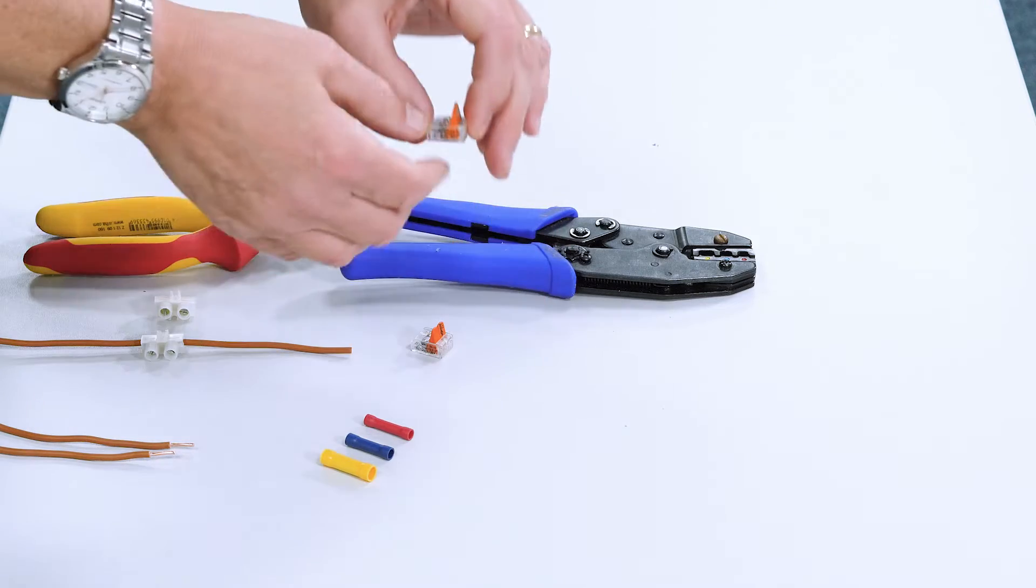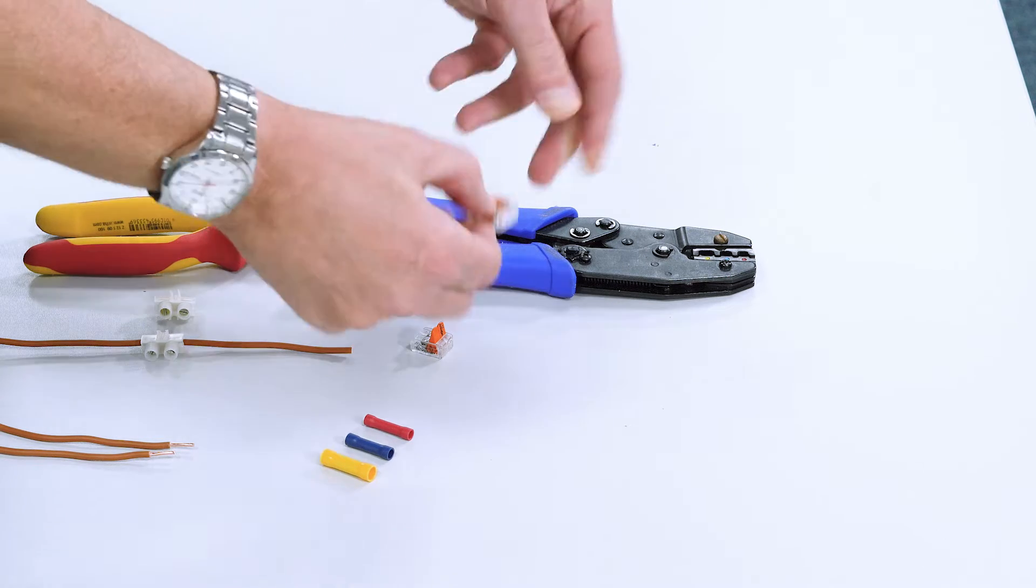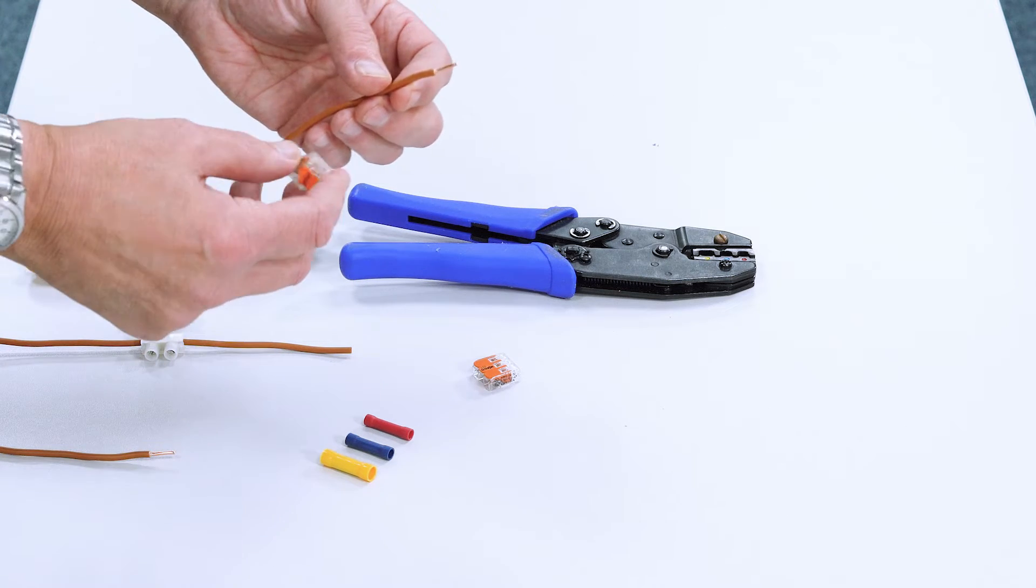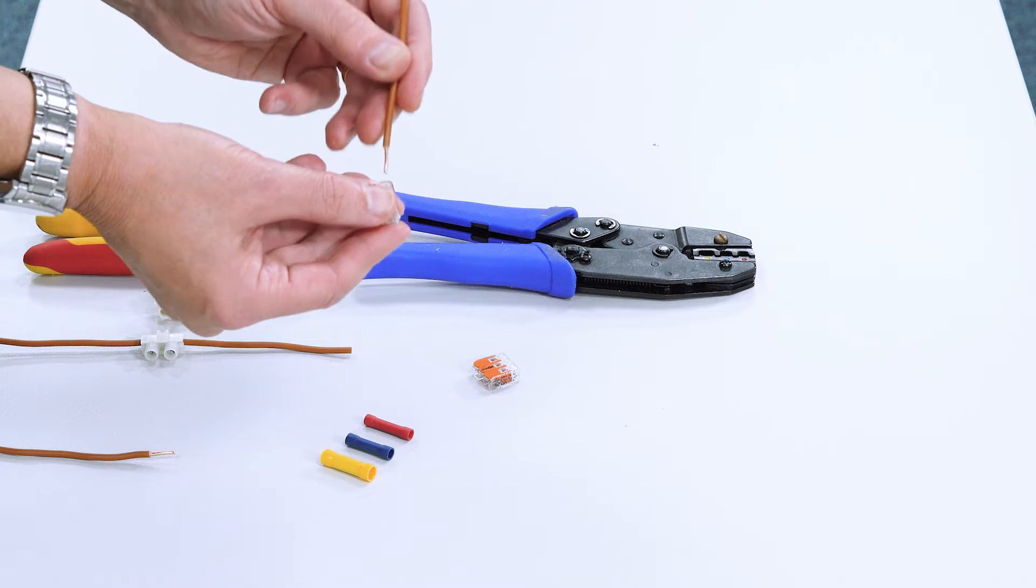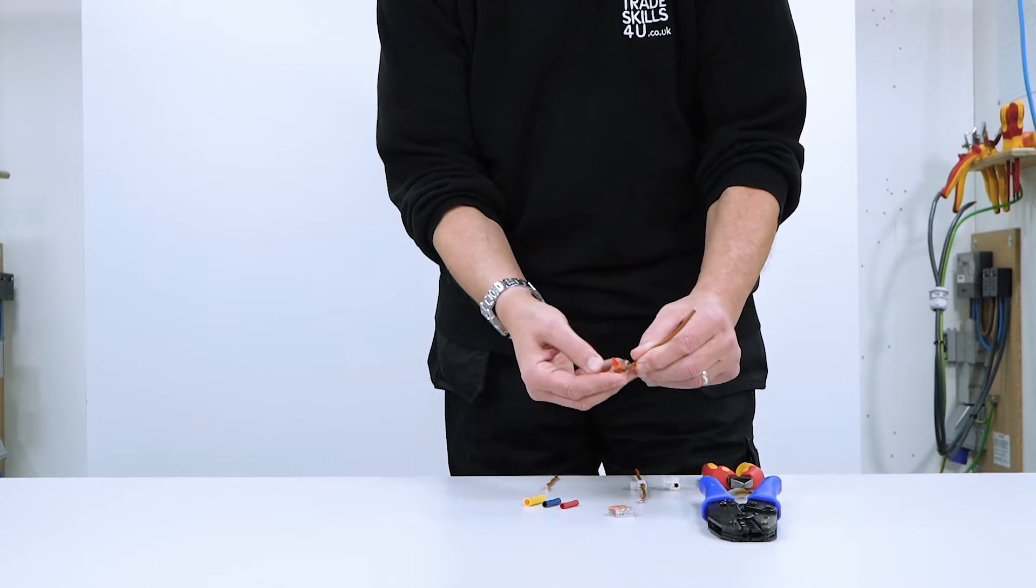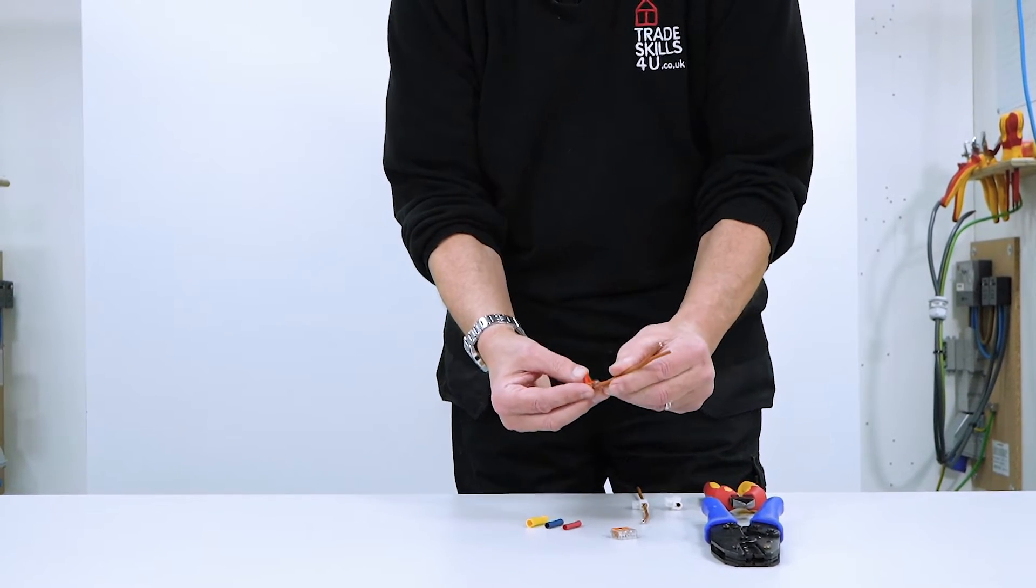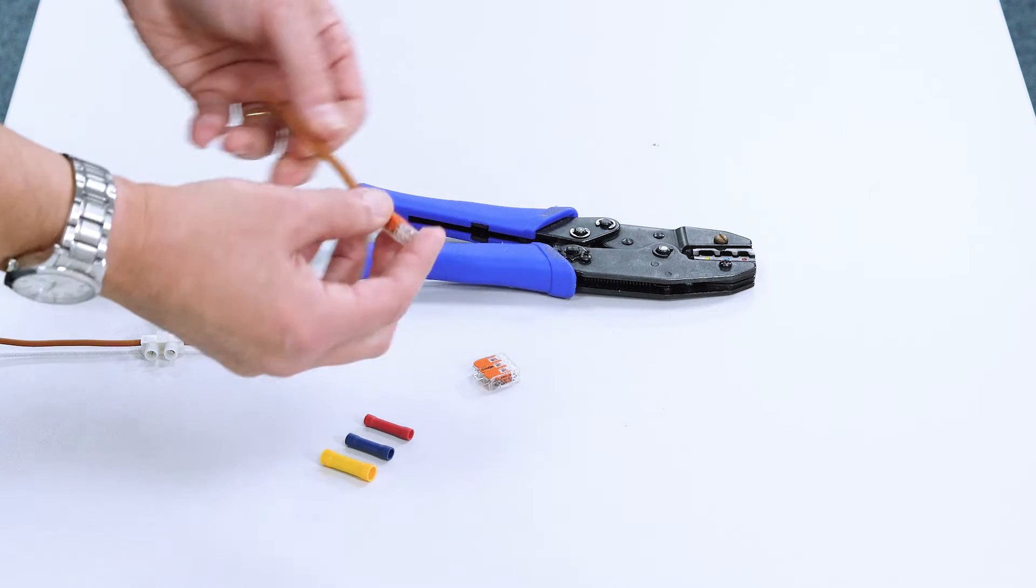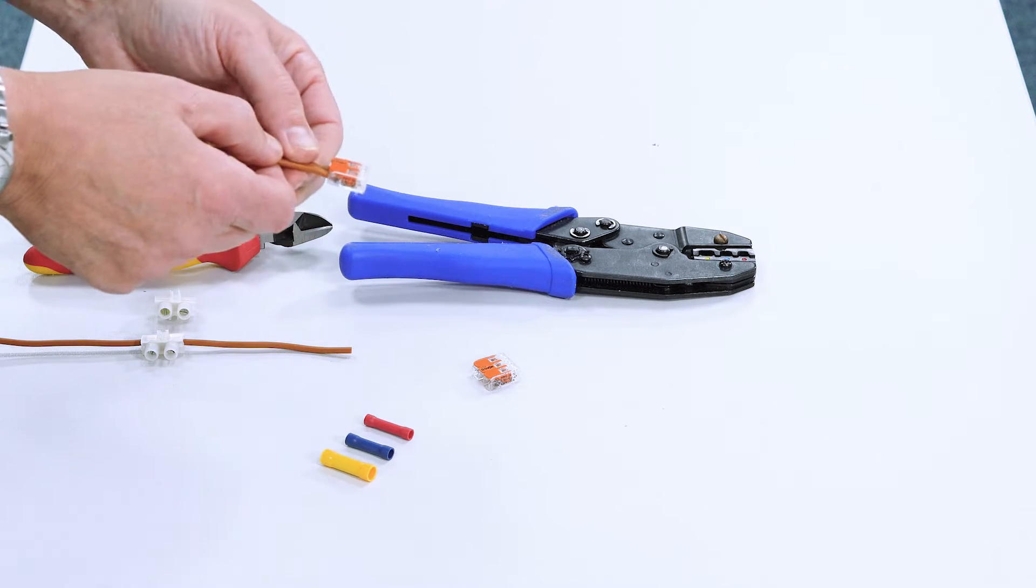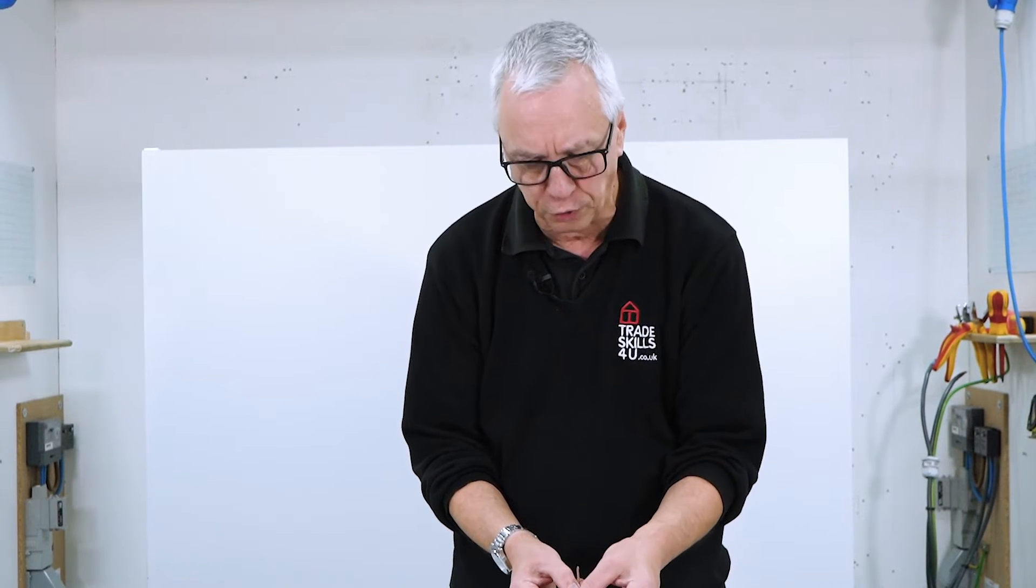We've then got the lever connector where you've got this thing where these levers push down. You've got to prepare your conductor to the right length that slides in there, make sure there's no copper visible and the lever clamps down there and hey presto, there we go. Nice join. These are great because they're so quick and easy to use. The problem with them is that they're a bit bulky so it could present a problem if you're tight on space.